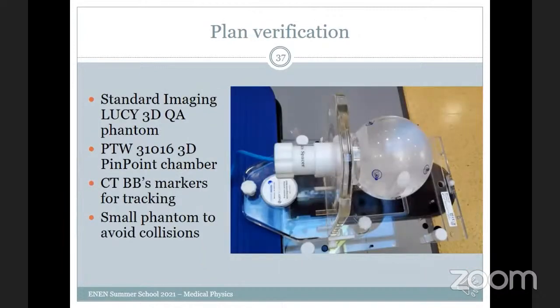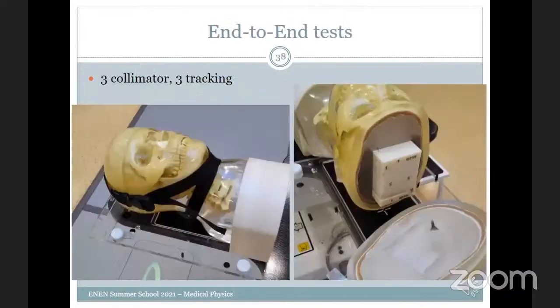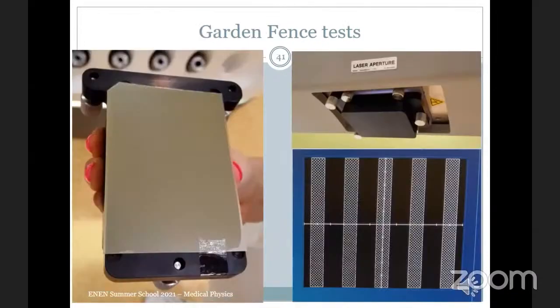With the plan verification we do patient-specific QA in a Lucy phantom with a very small ionization chamber. Before the treatment of every patient we have to measure every treatment to verify that the patient will receive the expected dose. With the end-to-end test, we have to measure the total targeting error of the machine for each collimator and for each tracking. The picket fence test is dedicated to the MLC calibration check.